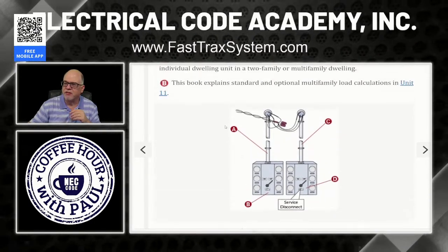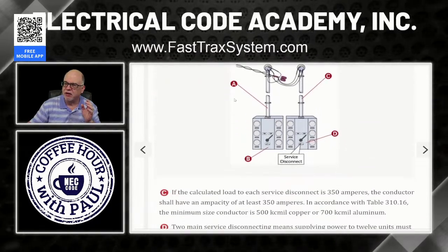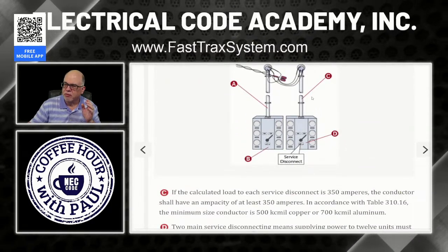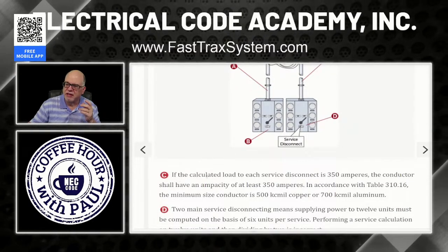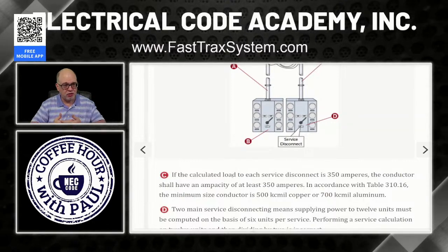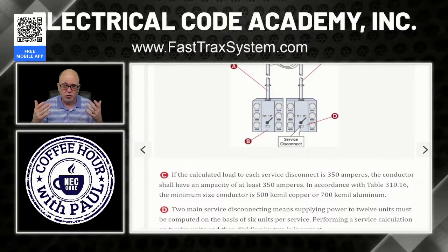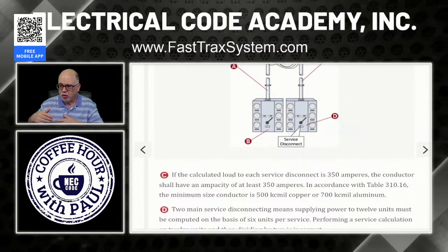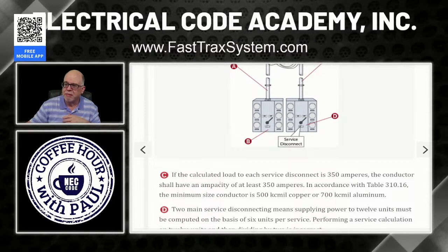All right, let's work this thing out real quick. Since we can't use 310.12, let's look at what we've got here. So C, which is pointing here, is just for reference. It says, now, if the calculated load, that means you did the math, you calculated it up, you used a worksheet, you used either part 3 of Article 220 using the standard method, or you used the optional method in part 4, however you did it, you came up with a calculation.